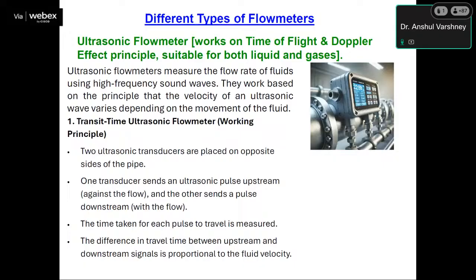It is suitable for both liquids and gases, and at NPL we are providing calibration for ultrasonic flow meters for water as well as gases. For water, we are covering the range from 10 liters per hour to 6 lakh 50,000 liters per hour, and for gas we are providing calibration for these types of flow meters from 1 standard cubic centimeter per minute to 2000 standard liters per minute.